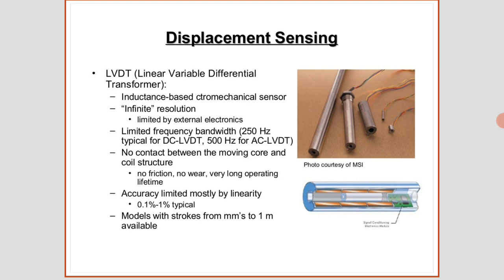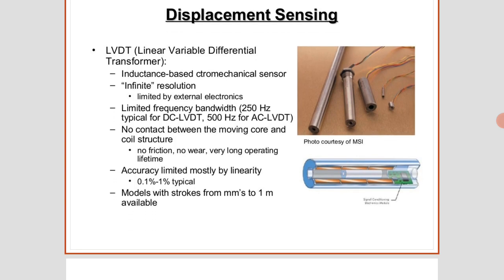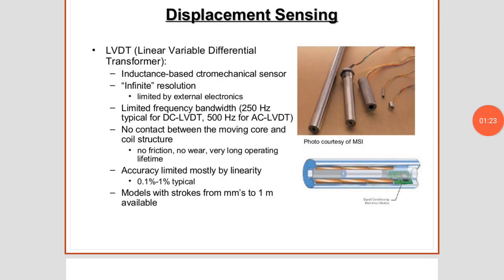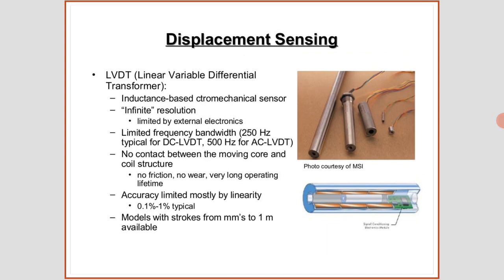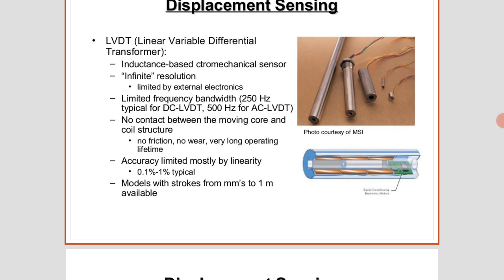In displacement sensing, LVDT, linear variable differential transformer, inductance based electromechanical sensor, infinite resolution, limited by external electronics, limited frequency bandwidth, 250 Hz typical for DC LVDT, 500 Hz for AC LVDT, no contact between the moving core and coil structure, no friction, no wear, very long operating lifetime, accuracy limited mostly by linearity 0.1% to 1%, models with strokes from mm to 1 m available.